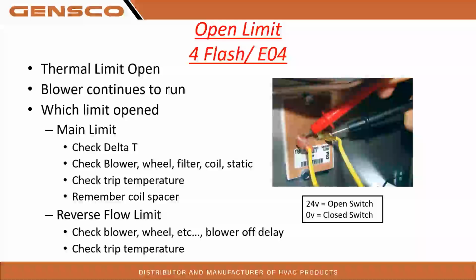Why are we hitting that? I would think on a 90% furnace, if we were getting reverse flow limits, I would think the secondary is impacted because we're holding heat tight to that blower motor, right? So we're going to look at all of these things in a 4-flash.